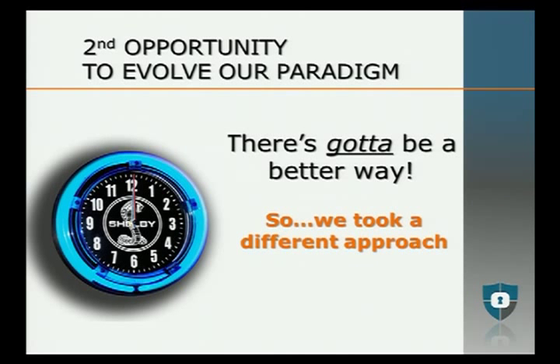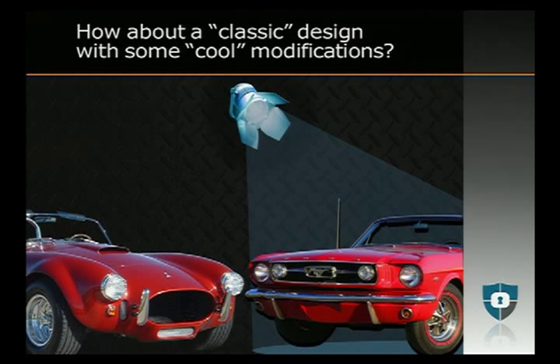The second time, we had a little extra time on our hands and were getting ready to expand another 33,000 square feet in the existing facility. So we thought, well, there's got to be a better way. We took a different approach: take the classic design and make some cool modifications along the way, try to drop that PUE down, and at the same time increase the kW on a per-rack basis to the IT end user.